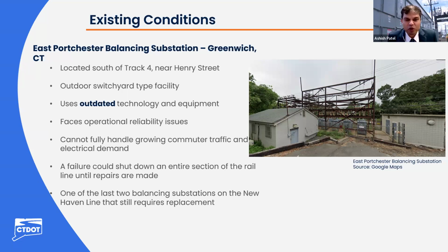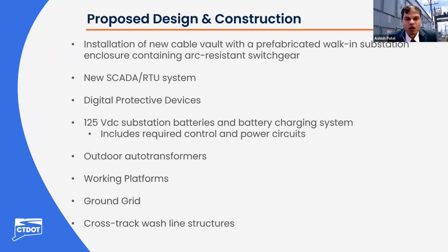As discussed earlier, the existing equipment is outdated and struggles with reliability. So any failure in the existing balancing substation could shut down the entire northeast corridor train traffic. Once the new substation is energized, the existing traction power equipment will be demolished and removed from the existing switchyard. The proposed design and construction steps for the East Portchester balancing substation are similar to what we discussed under the Sasco Creek balancing substation. However, this site does not have optimum available property adjacent to the existing balancing substation. The state of Connecticut is in the process of acquiring additional needed property from the adjacent property owner. The temporary easement is also needed for delivering the balancing substation and placing the crane on the adjacent property.